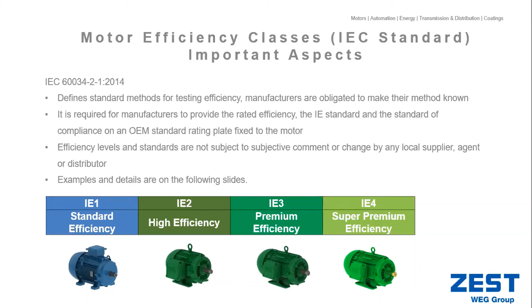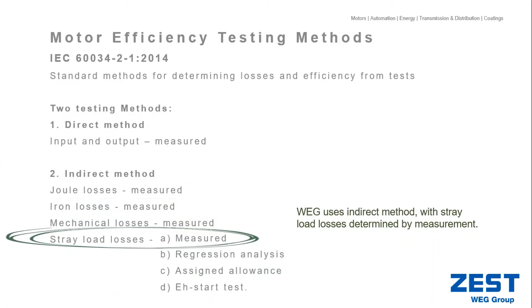I cannot take an electric motor that's got a specific rating and adapt it for South Africa and say now it's changed from IE2 or IE3. And again, I just show you at the bottom the different efficiency standards and classes that are currently available. So with testing methods, according to the standard, there's what we call a direct method, and there's also an indirect method. For us, we like to use the indirect method, and we will actually go and measure all the losses individually.